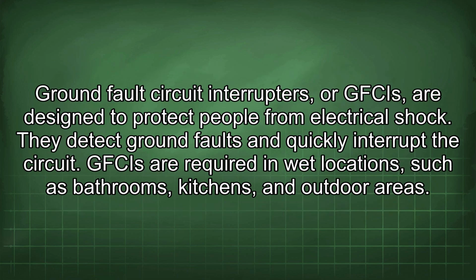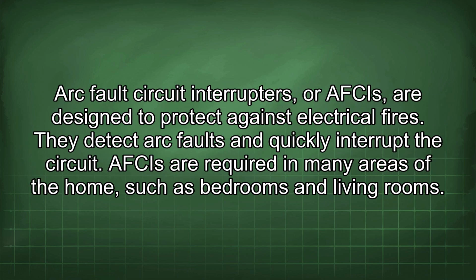Ground fault circuit interrupters, or GFCIs, are designed to protect people from electrical shock. They detect ground faults and quickly interrupt the circuit. GFCIs are required in wet locations, such as bathrooms, kitchens, and outdoor areas. Arc fault circuit interrupters, or AFCIs, are designed to protect against electrical fires. They detect arc faults and quickly interrupt the circuit. AFCIs are required in many areas of the home, such as bedrooms and living rooms.